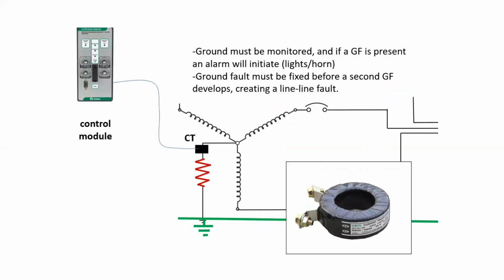Now, in a high impedance grounded system, typically what we have is a control module as well as a CT, and the CT is mounted so that the conductor that goes to the resistor goes through the CT. The ground must be monitored, and if a ground fault is present, an alarm will be initiated through lights or horn or something of that nature. Then it is a race against the clock. You want to try to fix the ground fault before a second ground fault develops, because you don't want a line-to-line fault.